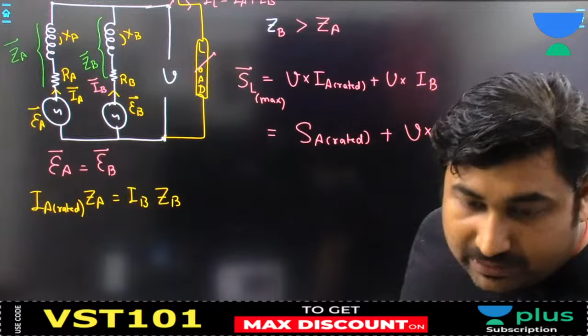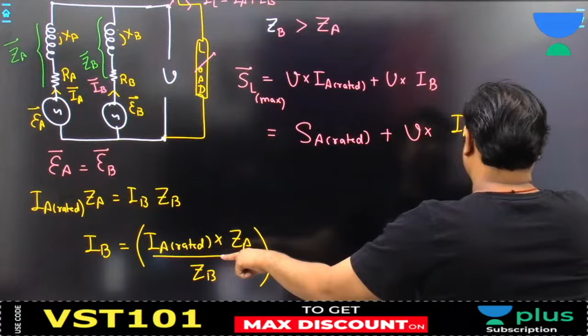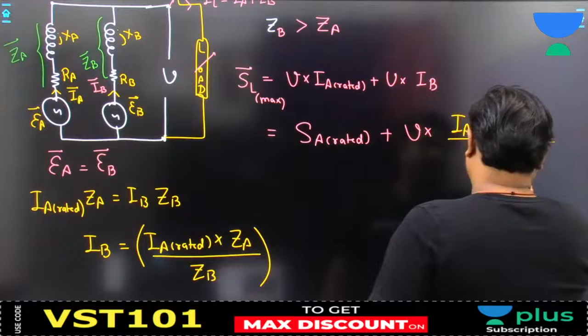So you can say, from here, operating current IB when the transformer parallel combination feeds maximum load is IA rated into ZA upon ZB. Can I write it this way? I am replacing IB by this equation: IA rated into ZA upon ZB, where ZA and ZB are in actual ohms.